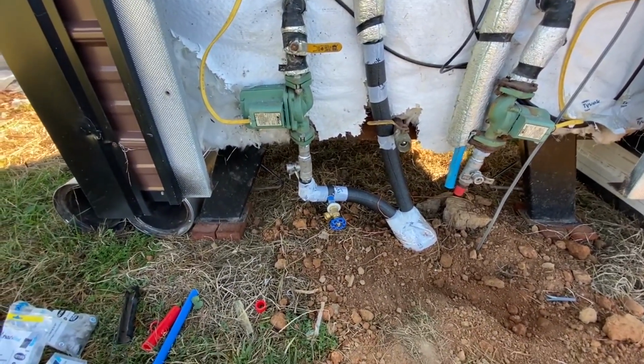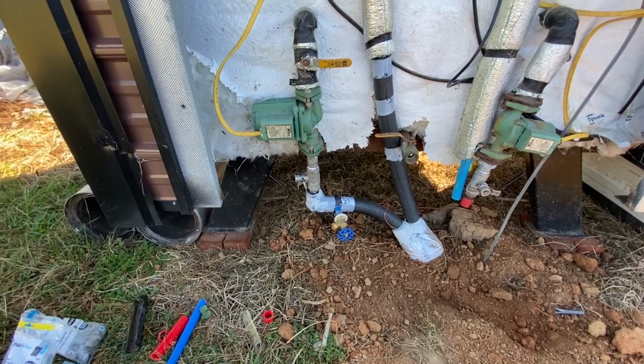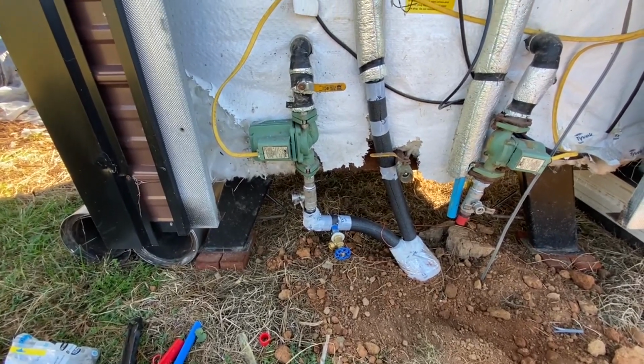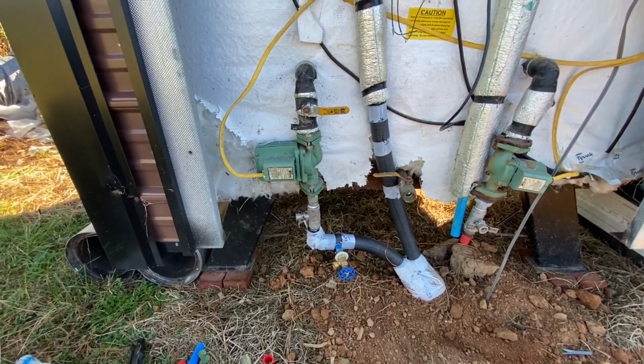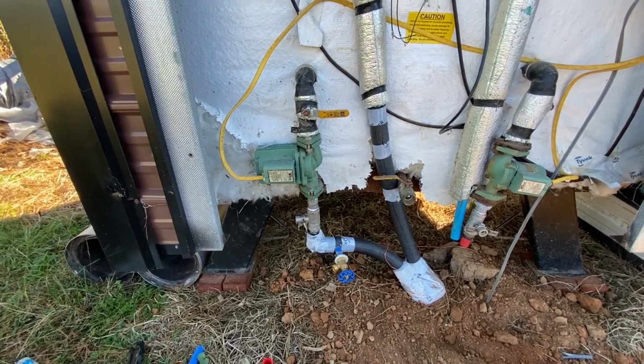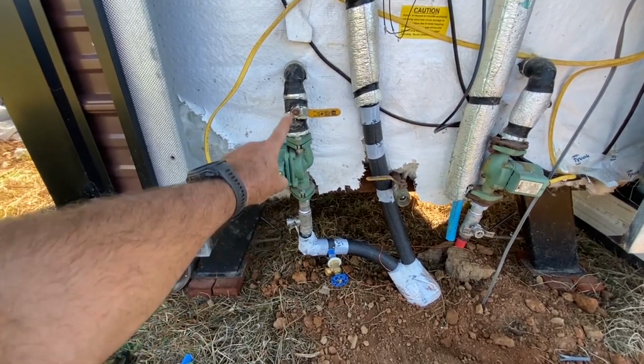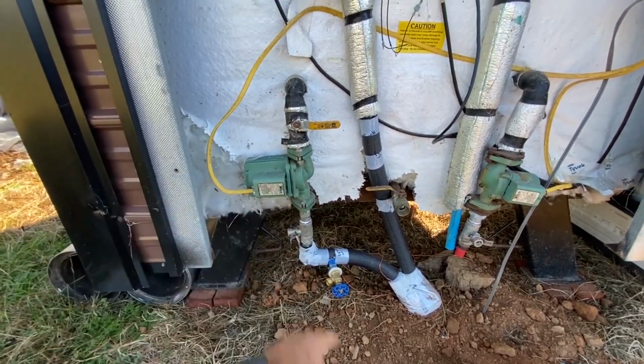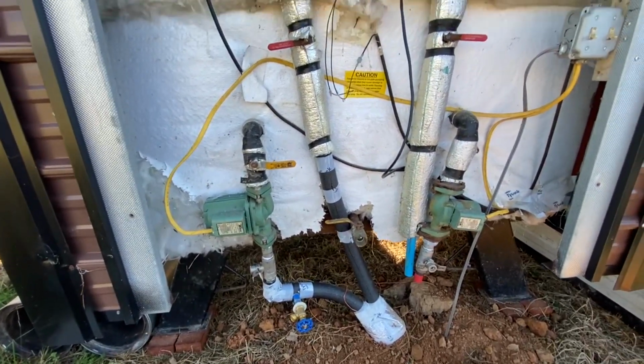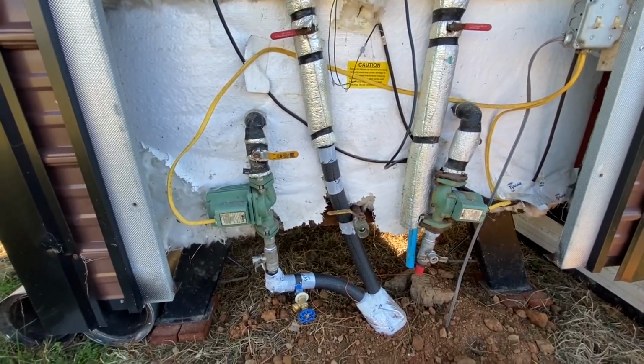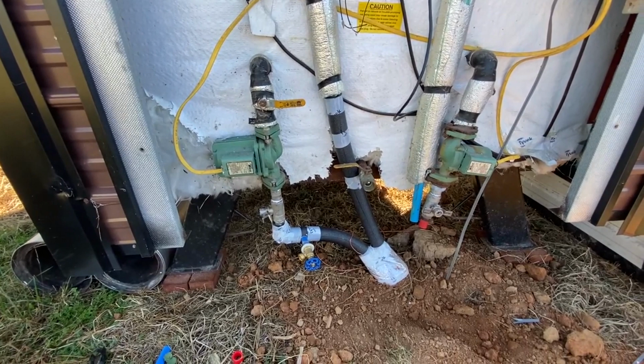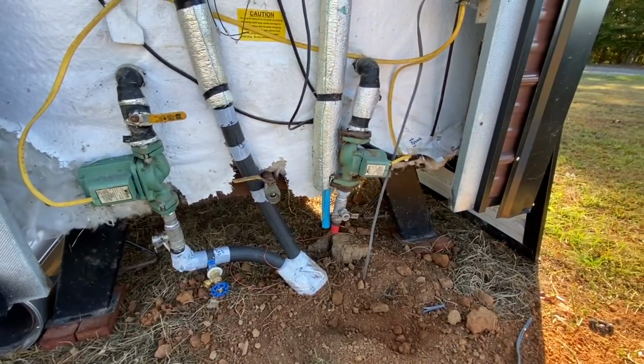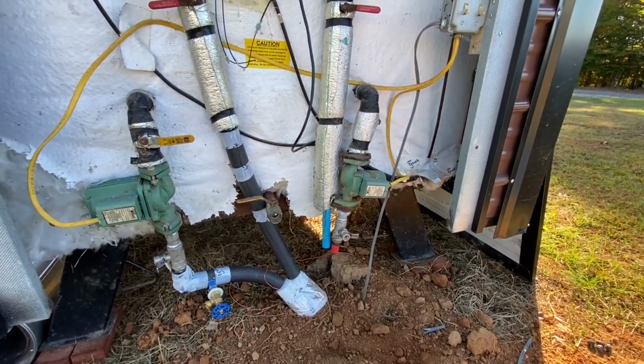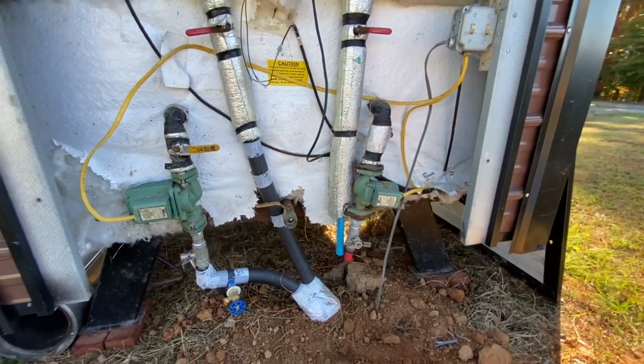The hot side has a pipe drain because I want to fill it from there, so I'm filling after the pump, so that after I'm done I'll have just a short section of air in that short pipe. The return, of course, goes to the top of the tank, and the tank is vented, so there's no need for a vent valve.